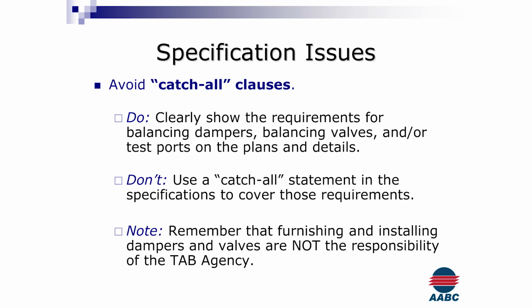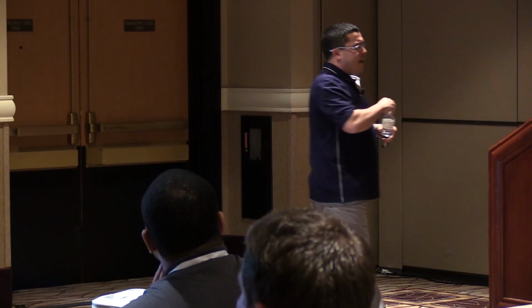Avoid catch-all clauses. I touched on this earlier, and this is that gray area where we're working on a hospital and we're doing 4 stories or 4 floors of it, but the system actually serves 8. And the catch-all clause, I've seen more than one occasion, and I always ask the question and send it back to the person requesting the bid: what does 'you will balance all outlets' mean? Does that mean all outlets shown on this drawing? Or is the engineer getting tricky and wants to get the whole system rebalanced with a very small catch-all note?